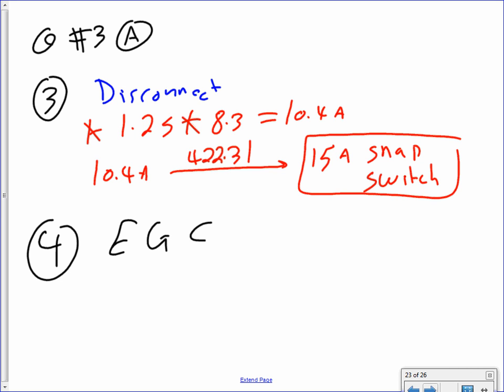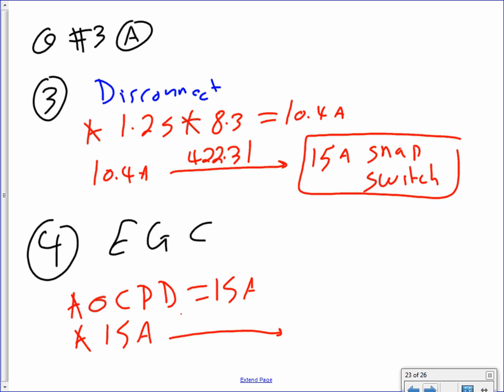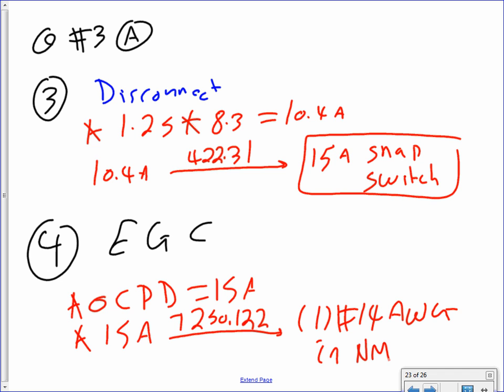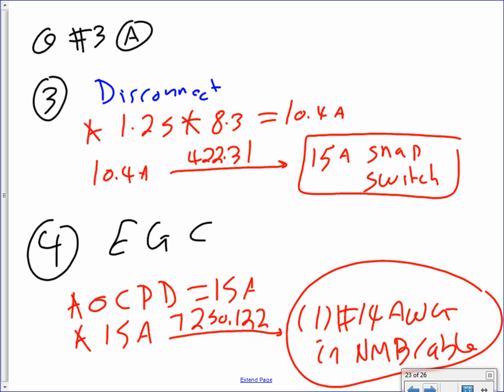Okay. The last thing is the equipment grounding conductor for this board. The equipment grounding conductor does the 20 amp, the 15 amp that we got. My overcurrent protection device was 15 amps. You take the 15 amps, table 250.122, right? That will get you one conductor, number 14 AWG, in an NM cable. So your equipment grounding conductor will be the number 14. Almost done.